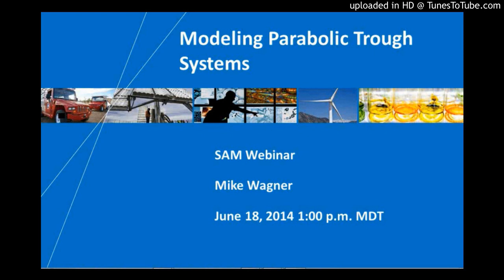now what we see is the best case is not actually building a huge amount of storage. It's quite a bit of storage in this case because we've got a direct system. But it's not just as kind of an open-ended slope. So here it actually turned out that our PPA price optimum was at 13 hours of storage with a solar multiple of about 2.8 or 3.